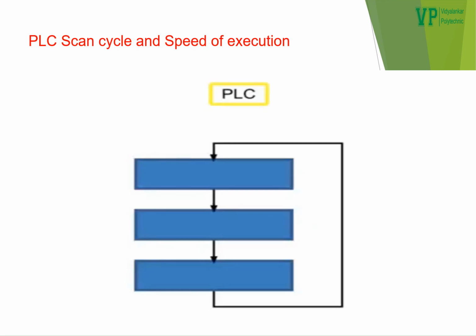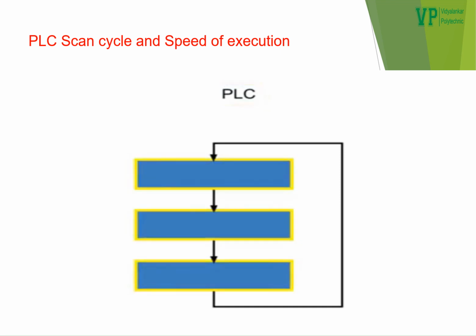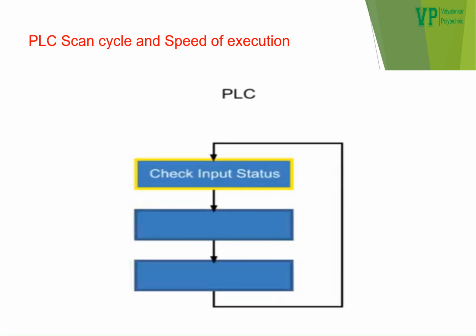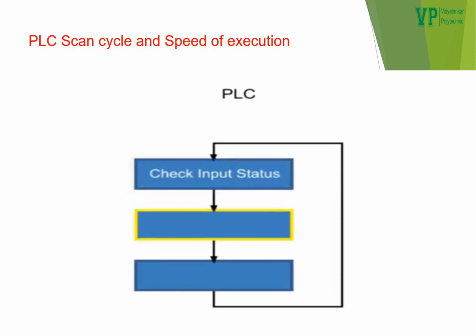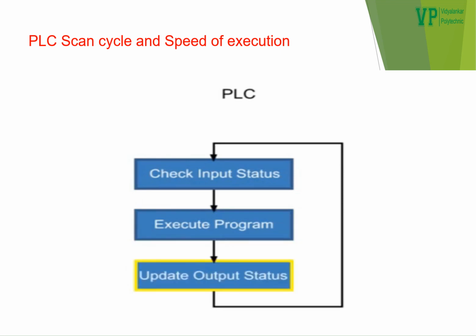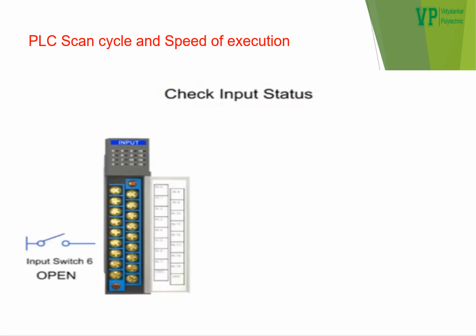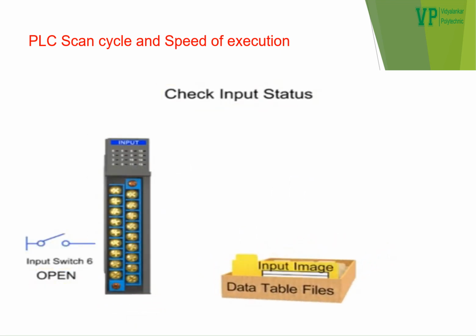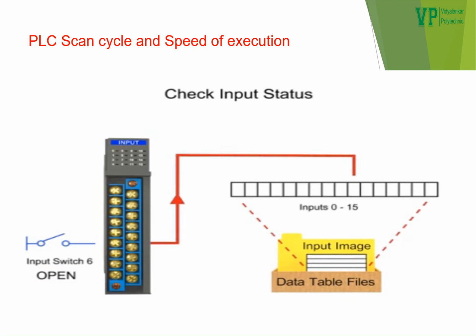Scanning cycle of PLC takes place in three phases. The first phase is check input status. The second phase is execute program. And the third phase is update output status. During the first phase of scanning, the status of input, be it open or close, gets updated in the input status file.